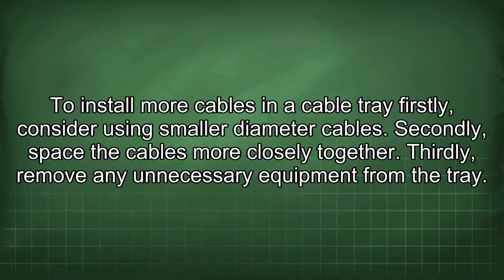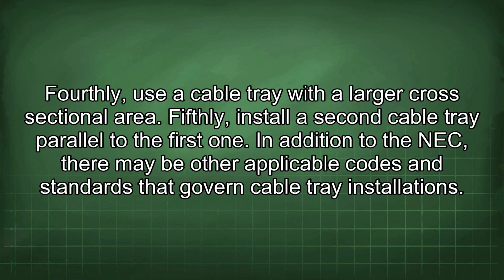To install more cables in the cable tray, firstly, consider using smaller diameter cables. Secondly, space the cables more closely together. Thirdly, remove any unnecessary equipment from the tray. Fourthly, use a cable tray with a larger cross-sectional area. Fifthly, install a second cable tray parallel to the first one.